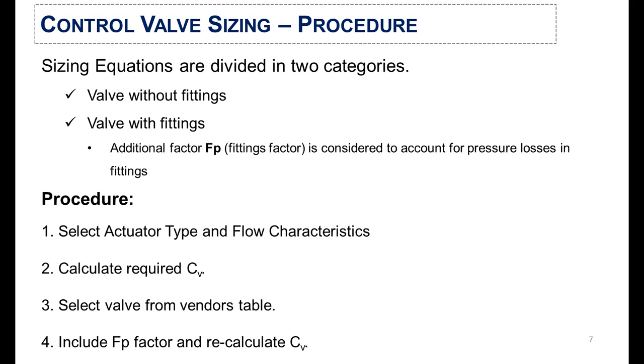Here comes the procedure of control valve sizing. Sizing equations are divided into two categories: valve without fittings and valve with fittings. If there are fittings across the valve, an additional factor called the fittings factor is considered to account for pressure losses. The main procedure steps are: first, select the actuator type and flow characteristics; second, calculate the required Cv (valve coefficient); third, select the valve from the vendor's tables based on the calculated Cv; and fourth, include the Fp factor (fittings factor) and recalculate the Cv.